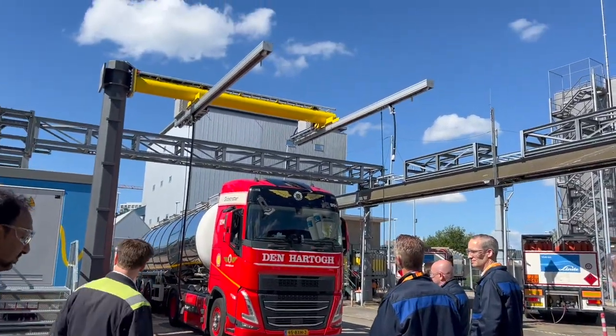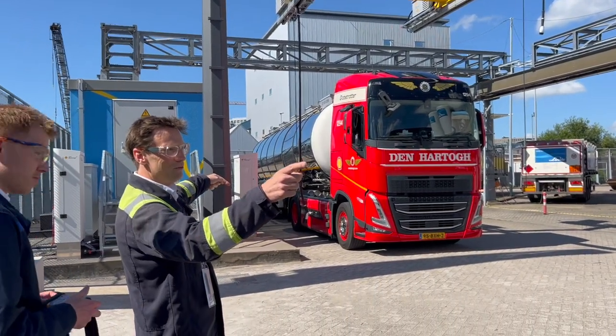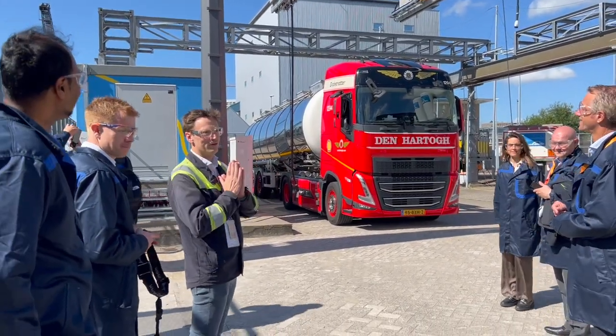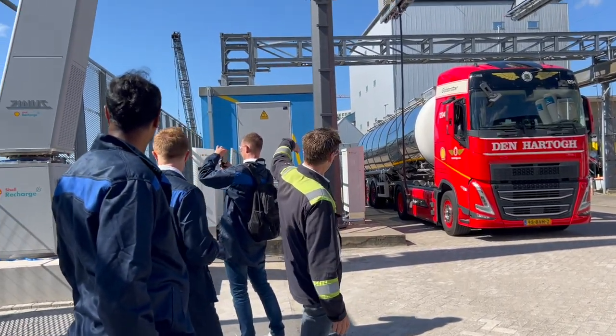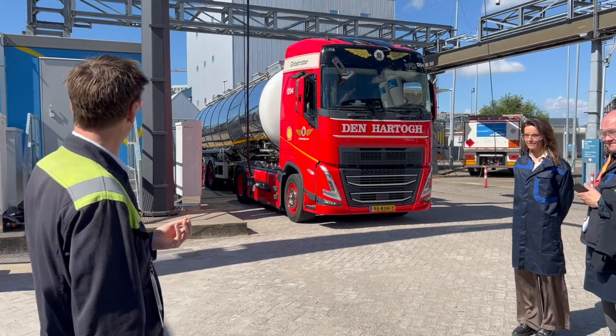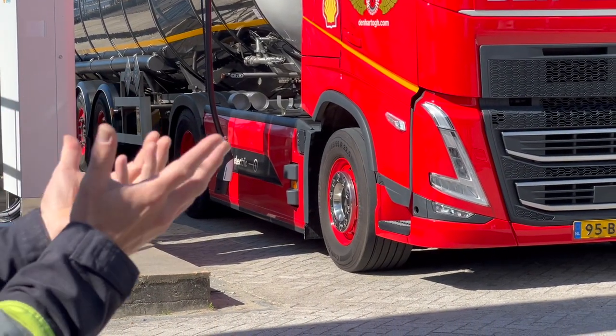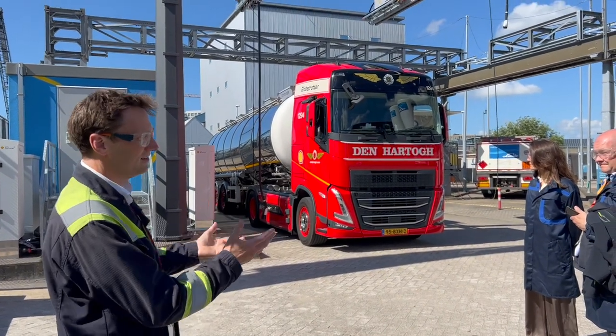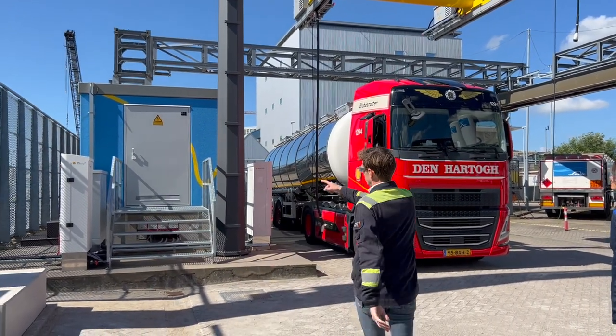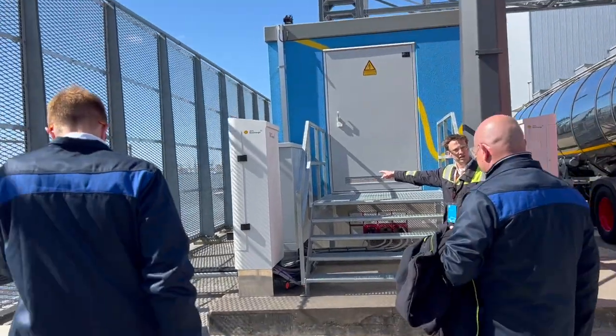I'm actually standing here on the tank line — it runs on the back of the building. Martin over there is really the guru and main designer of this whole system. The power comes in, goes through the transformer, steps down to 1,250 volts in one step — something we're very proud of. It then goes through the power electronics with the rectifiers, all of which is also liquid cooled, making it very efficient and very reliable with a long lifetime.